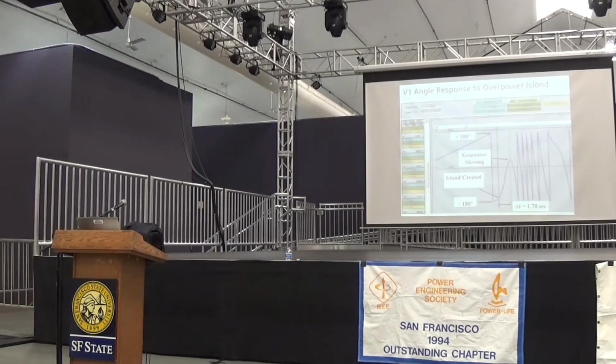Now, I'm not going to go into synchrophasors here, but suffice to say, the increasing angle means the generator is accelerating. The decreasing angle means that the generator is slowing down. And so what we see here is the actual dynamic response of the machine. In fact, knowing this information, I can actually compute the inertia of this entire plant.